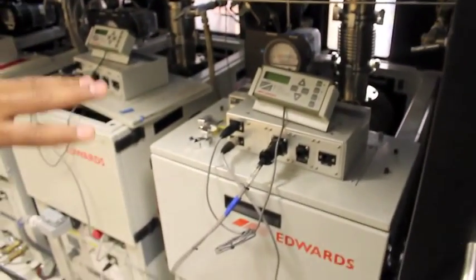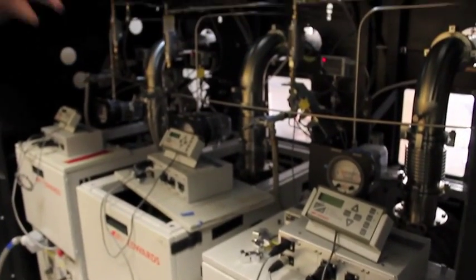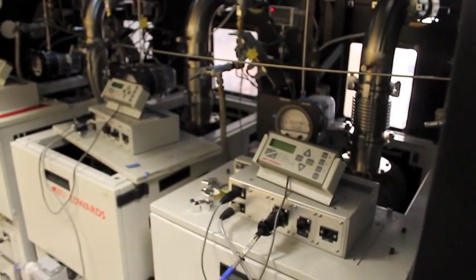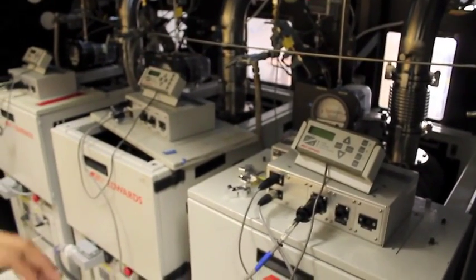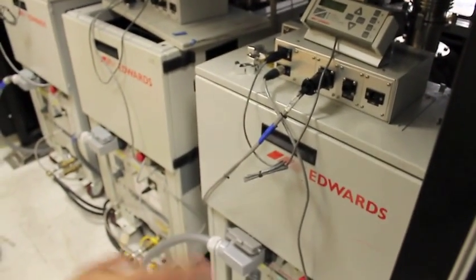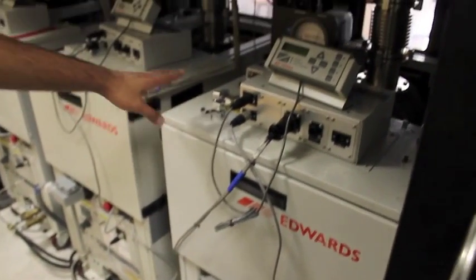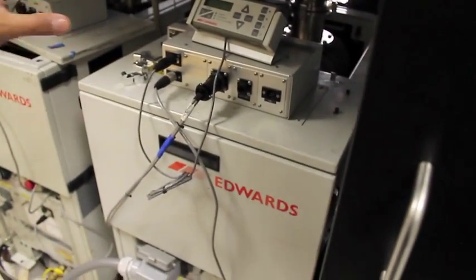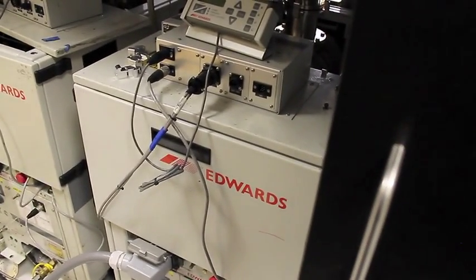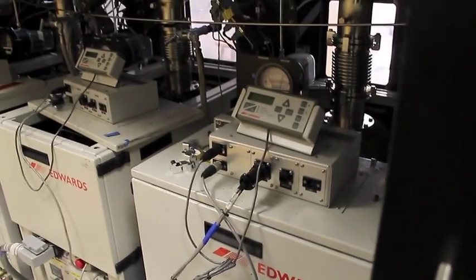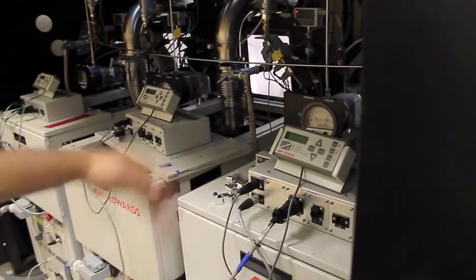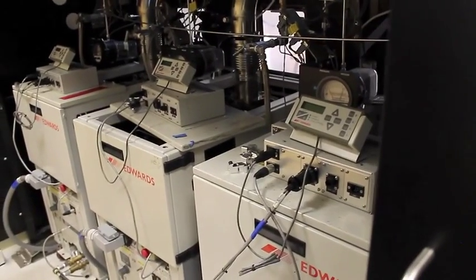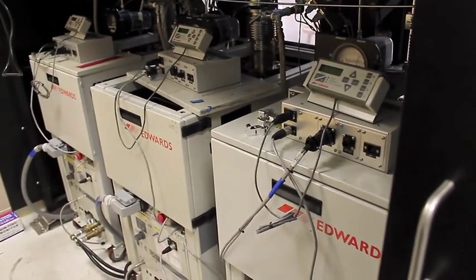This is the front view of all the pumps. The pumps have nitrogen dilution to dilute the gases that come out from the exhaust. They have water, nitrogen connected to them. These are Edwards pumps, which are state-of-the-art, really good quality pumps. They can be controlled remotely from the software, or directly from here, as desired by the user.